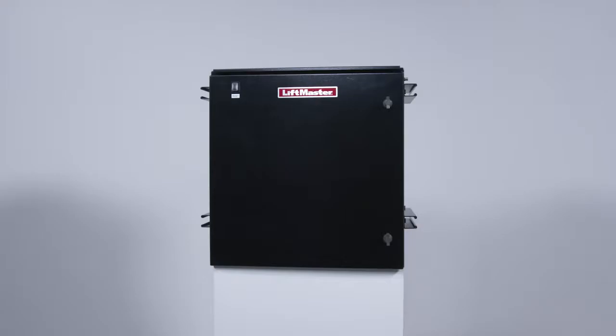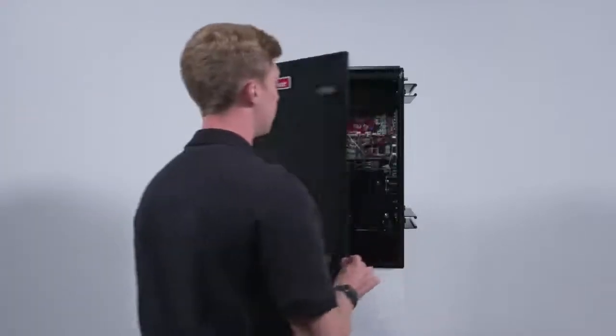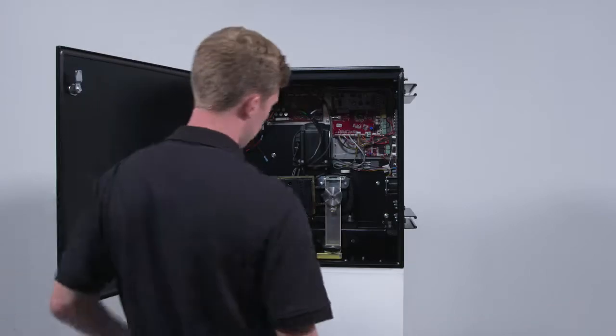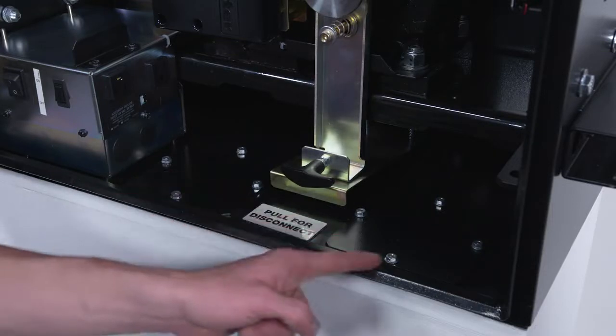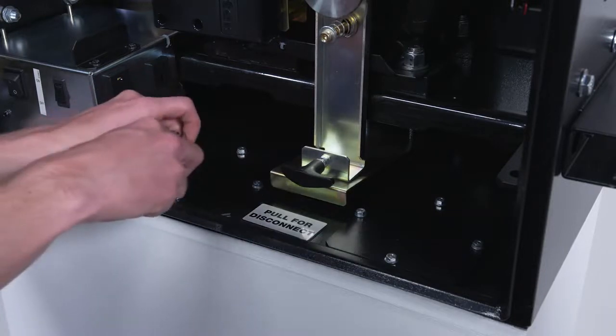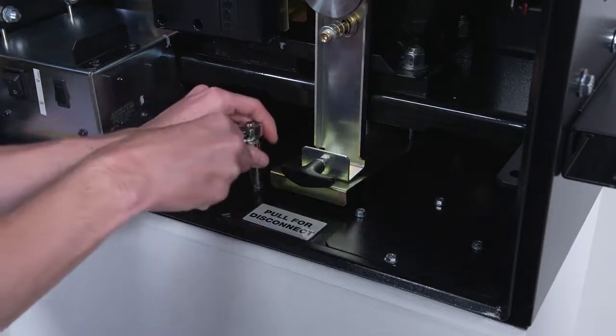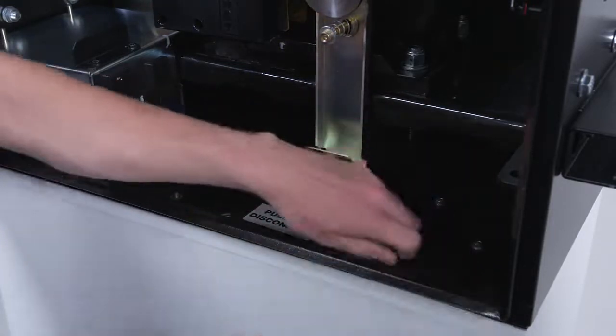First, we need to create access holes for the conduit for power and control wiring. Either at your shop or at the job site, open the operator. Locate the access plates. There are two. Either can be used to route power or control wiring into the operator. The power wiring must be run through a separate conduit from the control wiring. Remove the plates and drill a hole that is appropriately sized for the conduit of your site application.